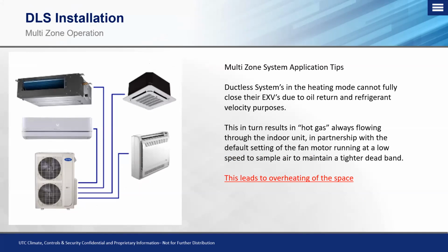that during the heating mode, the multi-zone ductless systems and also the single-zone ductless systems cannot shut their EXVs 100%. The reason we cannot shut them 100% is because we can facilitate long piping lengths. Oil return is crucial on these systems, so we have to maintain a minimum position so that we get a constant refrigerant and, more importantly, oil flow or circulation out through the system and back to the compressor.